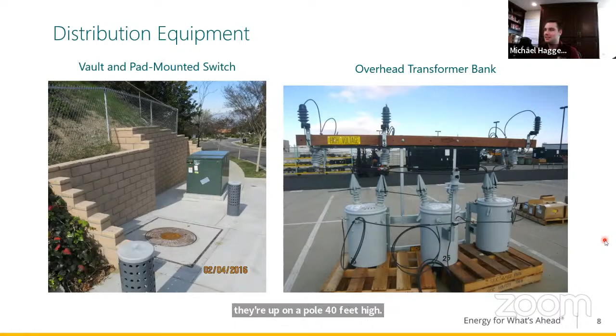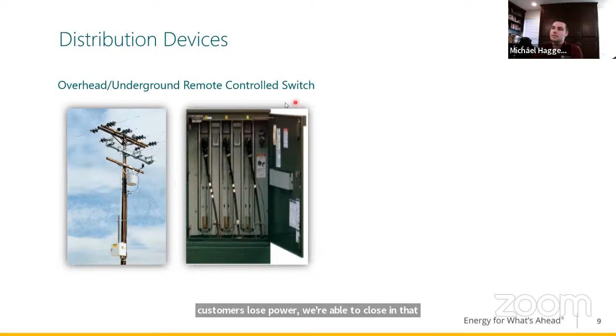So a couple more of our devices, some things you might see around are these poles with white boxes on the side. That's some sort of automation. Here we have a pole switch that's being automated, what we'd call a remote control switch. These are deployed all over and often used as circuit ties, where two circuits meet. That remote control switch will normally be open, but if there's an event like a wire down or customers lose power, we're able to close in that switch and feed those customers from a different circuit. This is an underground remote control switch.